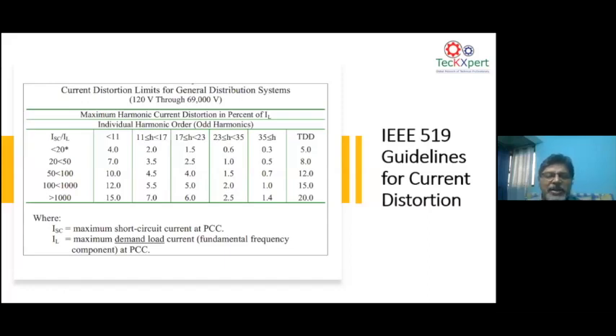Here, if your network is stable and strong, then you can permit a consumer to inject up to 20% harmonic current distortion, because your short circuit level is very high. But if it is weak, where a load is at a very long distance on a power line, where the voltage quality or stability is a problem, and where the short circuit level is very low, there you have to tell the consumer, sorry, I cannot permit you more than 5%. So current harmonic distortion limit goes by the short circuit level at the point where the consumer is connected.